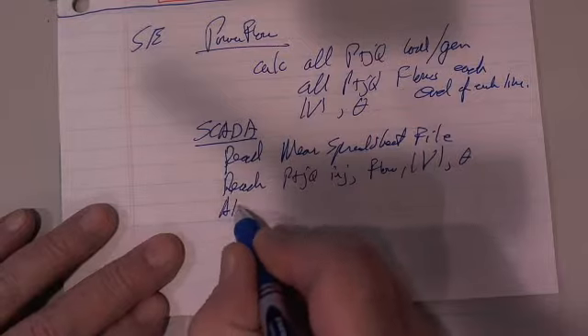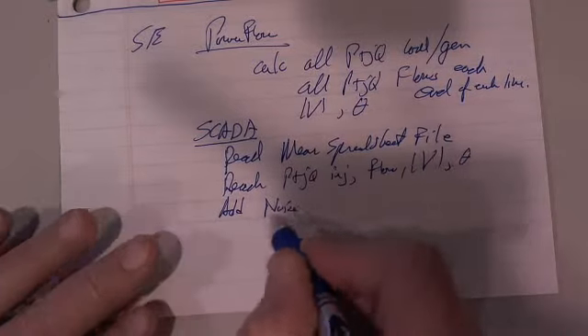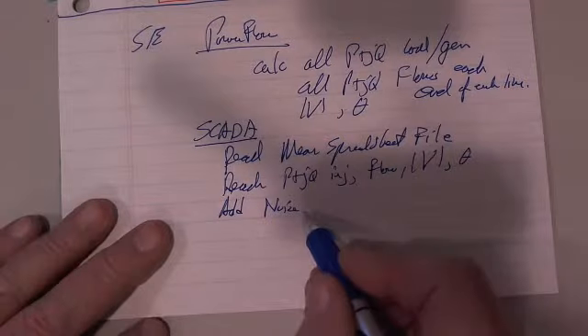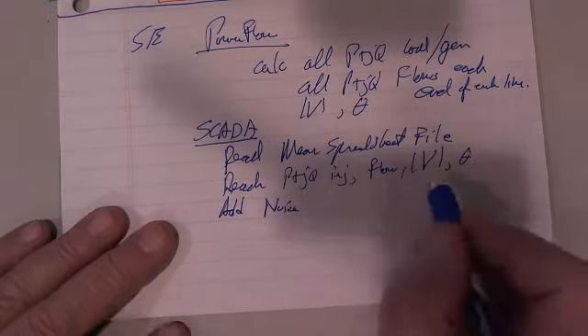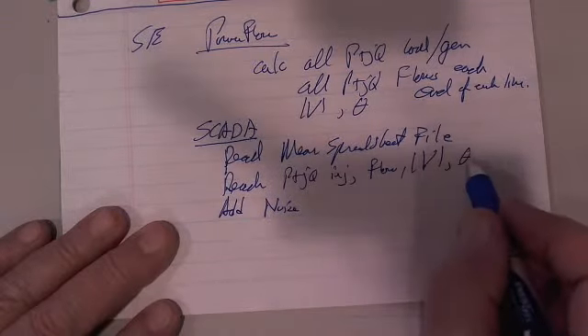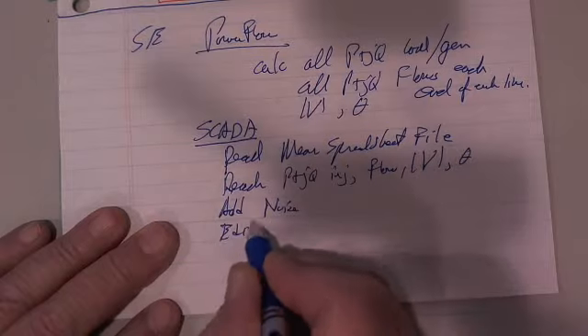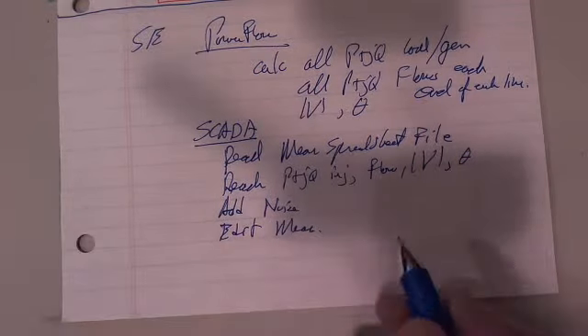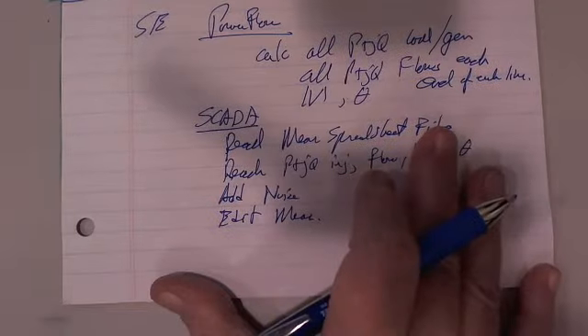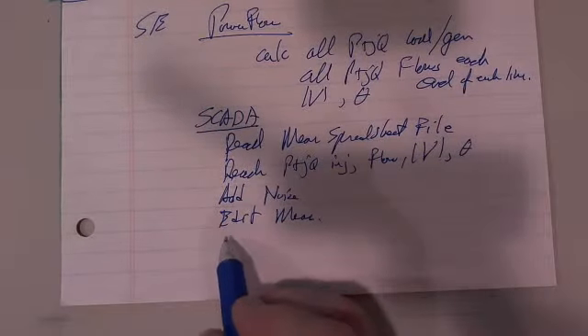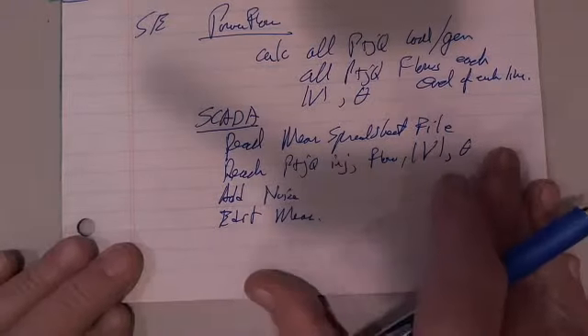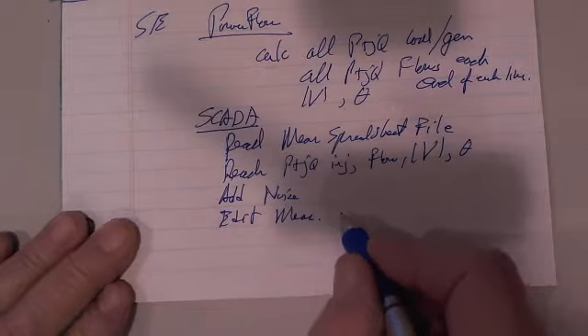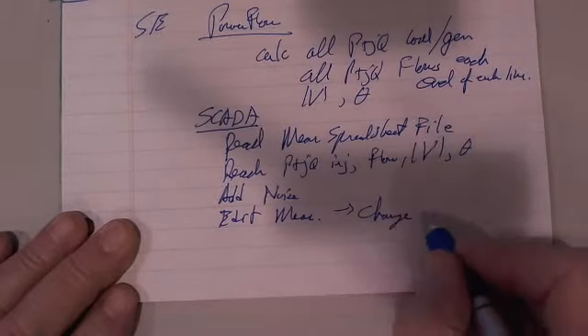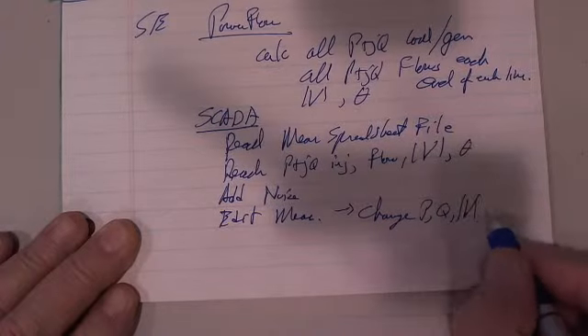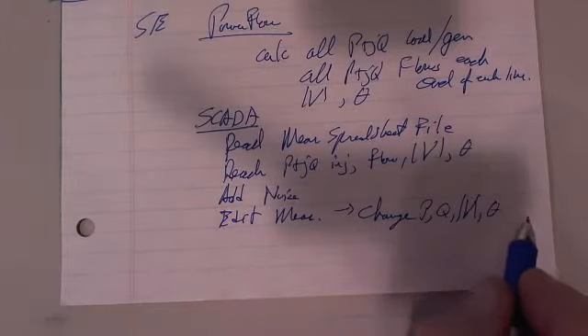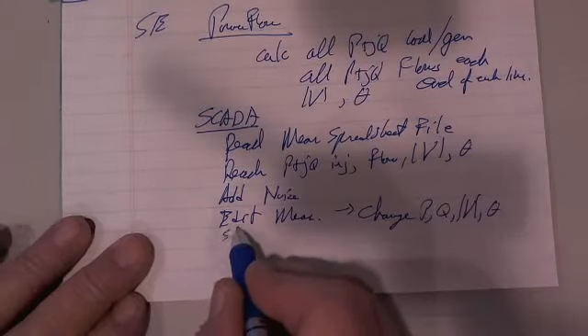Then you can add noise. We take the sigma that's specified in the measurement data, and we produce a random noise proportional to that sigma, and we put it on each measurement, okay? And you can also edit measurements. Unfortunately, one of the things I discovered as I was doing this that I probably should have put in was to be able to turn the measurement status on and off, but I didn't do that. So we can't do that, but you can edit the measurements. That means you literally change the P or the Q or the voltage magnitude or a phase. You change the value in there, and then you store it.